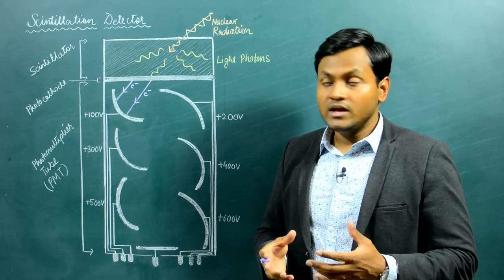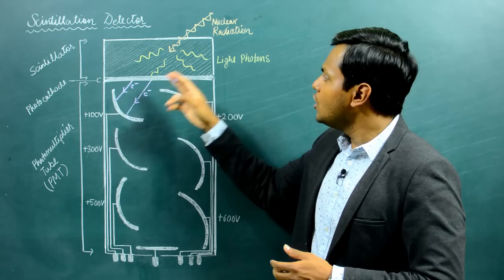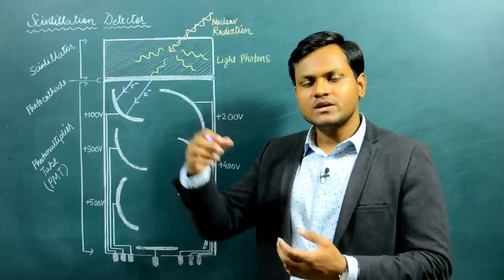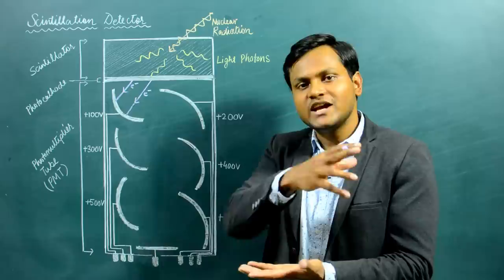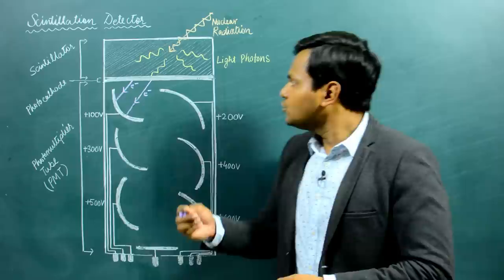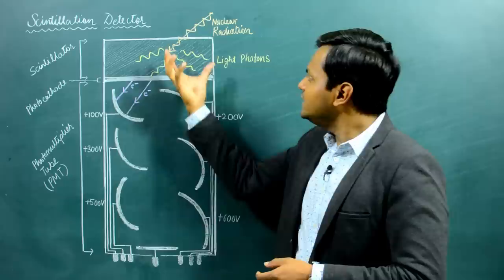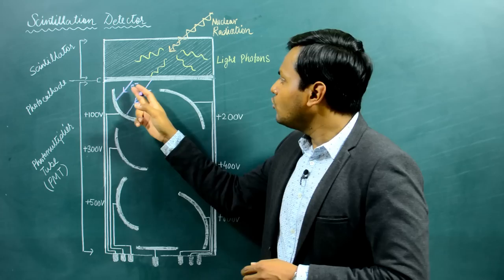All of these photons are focused onto a photo cathode. The photo cathode is simply a material that can experience the photoelectric effect. Whenever incident photons fall onto a metal surface and the energy of the photons is sufficient, electrons are ejected from the metal surface — this is the photoelectric effect. A photo cathode material is placed on top of the photomultiplier tube. When the light photons created as an incident particle enters the scintillator are focused onto the photo cathode, it results in the photoelectric effect and the emission of primary photo electrons.